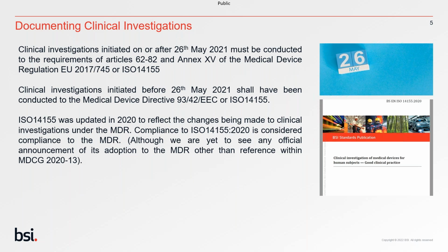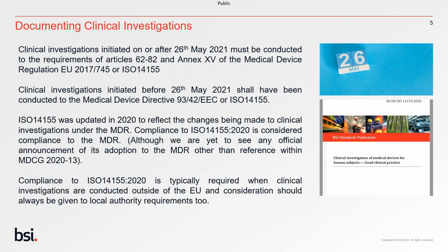Although we are yet to see this formally adopted or a formal announcement from the European Commission, we know that it has been adopted, or at the time was adopted, for the Active Implantable Medical Device Directive. There are some statements out there, but as notified bodies, we are still waiting for that to be adopted, but that doesn't say you cannot use ISO 14155 right now. It is still applicable and should still be considered, particularly where investigations are being conducted outside of the EU.